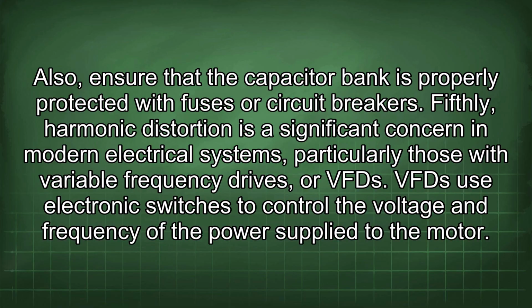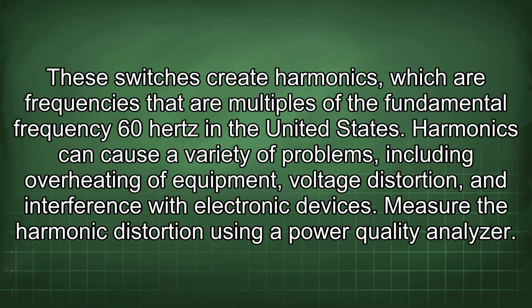Fifthly, harmonic distortion is a significant concern in modern electrical systems, particularly those with variable frequency drives, or VFDs. VFDs use electronic switches to control the voltage and frequency of the power supplied to the motor. These switches create harmonics, which are frequencies that are multiples of the fundamental frequency, 60 Hz in the United States. Harmonics can cause a variety of problems, including overheating of equipment, voltage distortion, and interference with electronic devices.